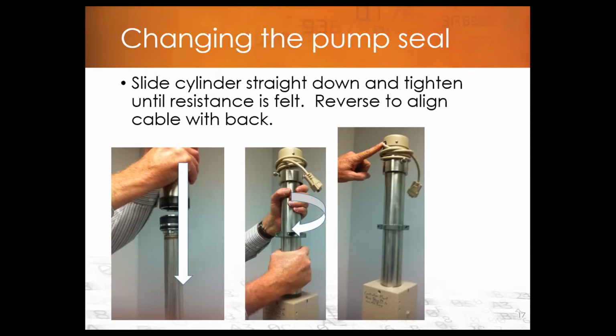So you'll tighten it down all the way until it bottoms out, and then you want to make sure you back it off probably at least a half a turn or more until your pressure transducer cable is coming straight out the back and your ports are lined up perpendicular.